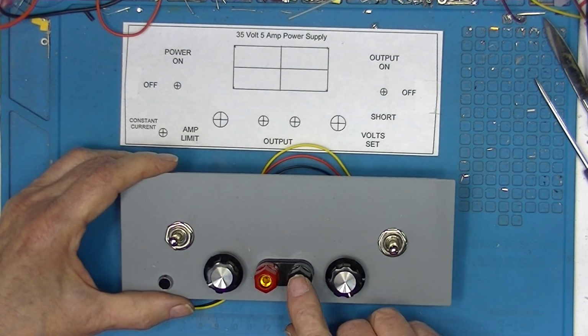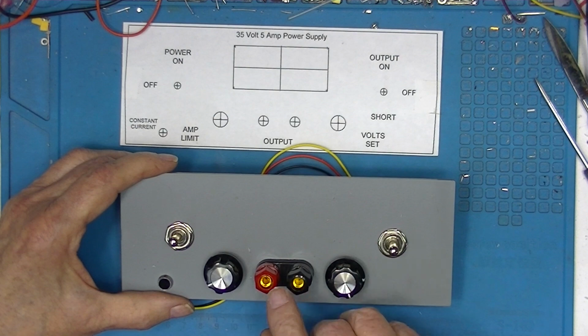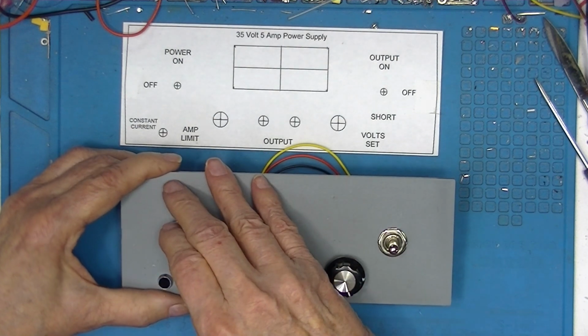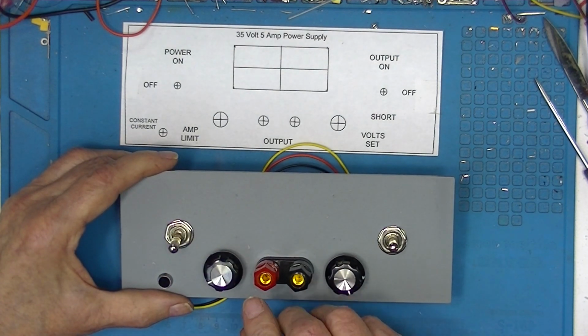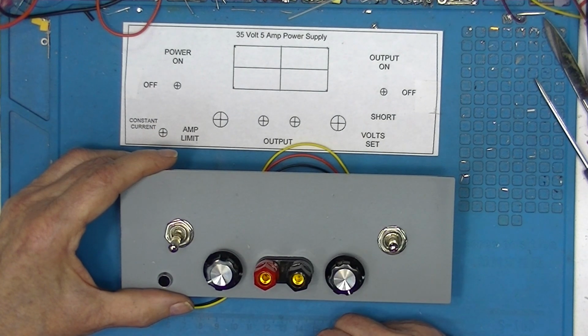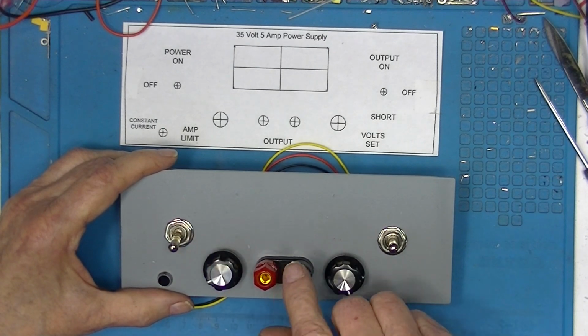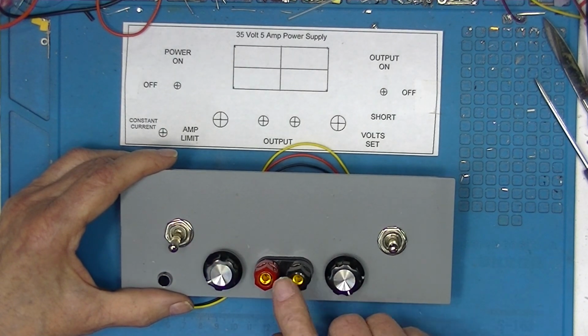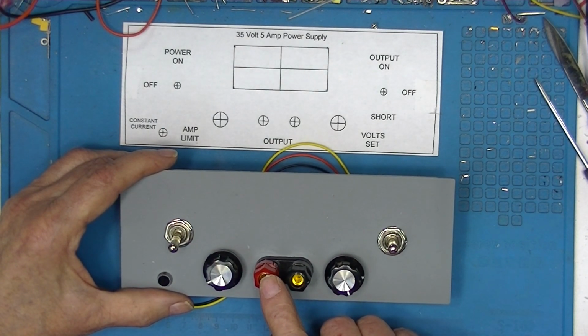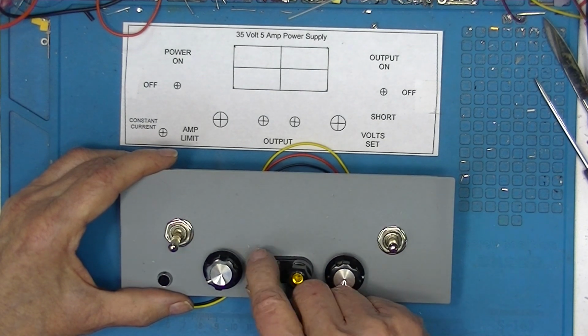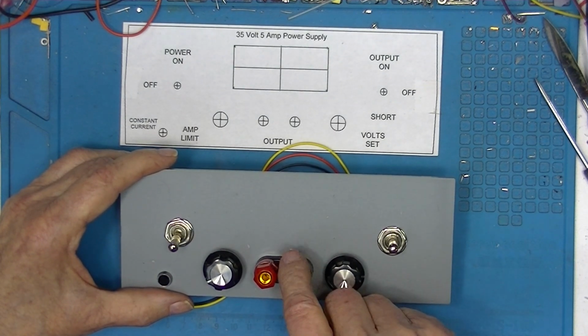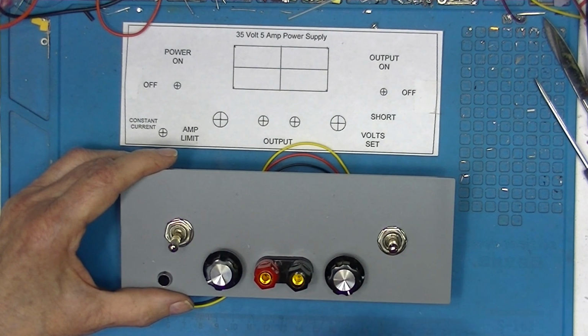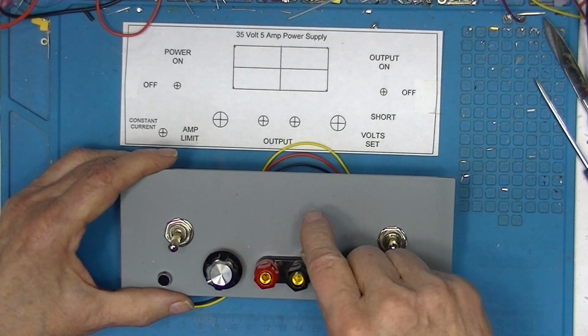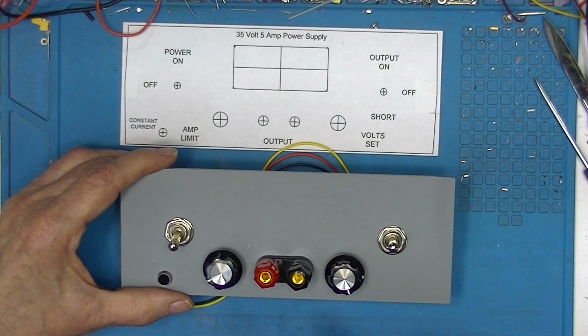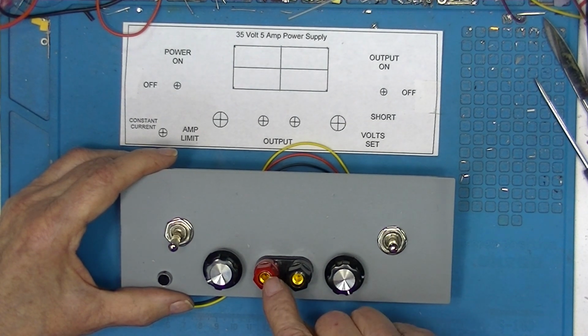If you had a fairly light load on this and turned the power supply off, it's possible the control system would lose voltage before this system. There are bleeders across the filter capacitors and the output, but the bleeders and the current being drawn may not be enough. Once you lose the control voltage, this voltage and current is unpredictable.